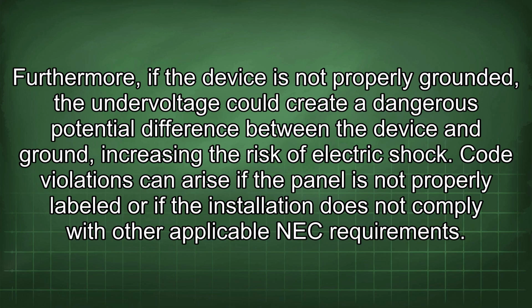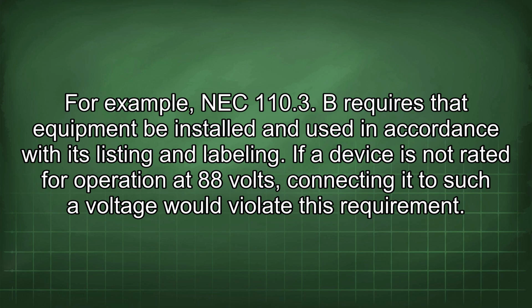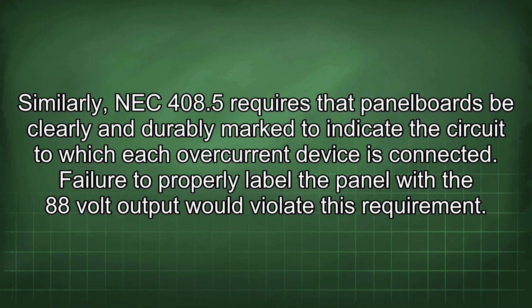Code violations can arise if the panel is not properly labeled or if the installation does not comply with other applicable NEC requirements. For example, NEC 110.3(B) requires that equipment be installed and used in accordance with its listing and labeling. If a device is not rated for operation at 88 volts, connecting it to such a voltage would violate this requirement. Similarly, NEC 408.5 requires that panelboards be clearly and durably marked to indicate the circuit to which each overcurrent device is connected. Failure to properly label the panel with the 88 volt output would violate this requirement.